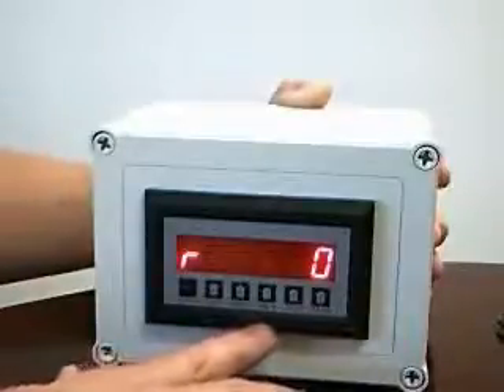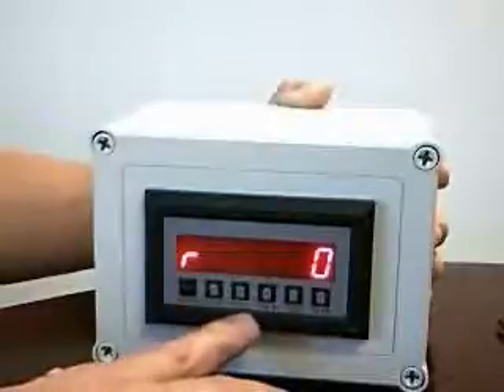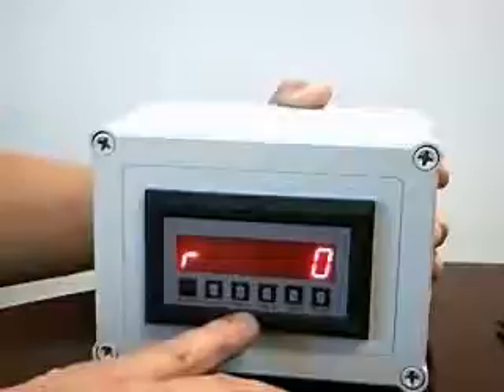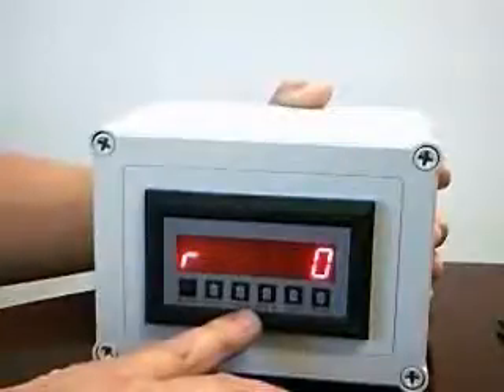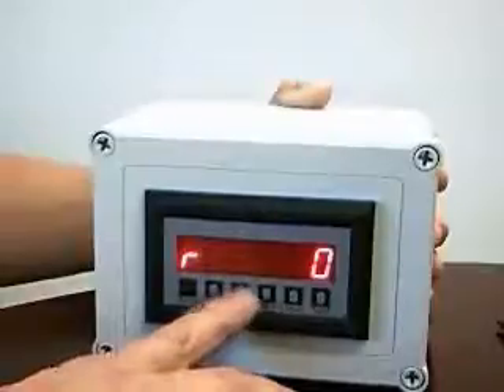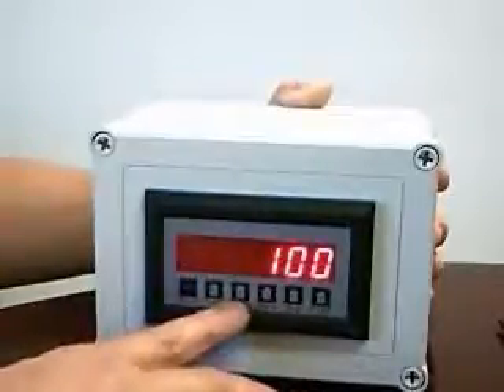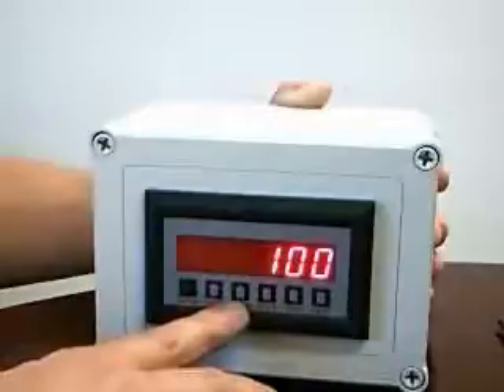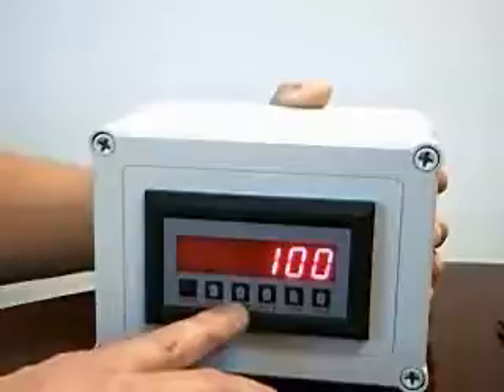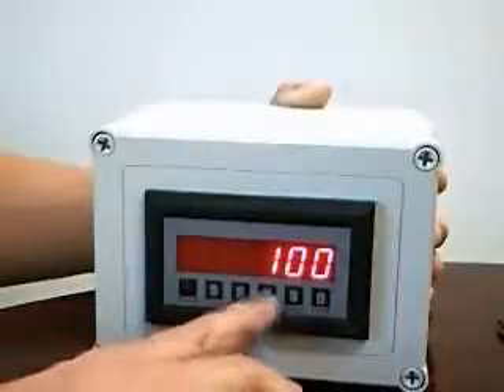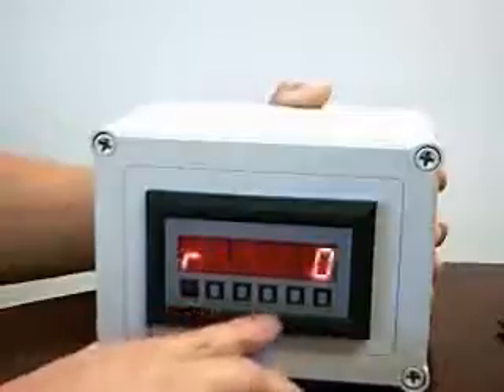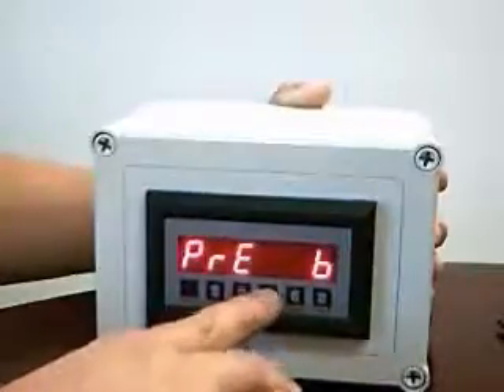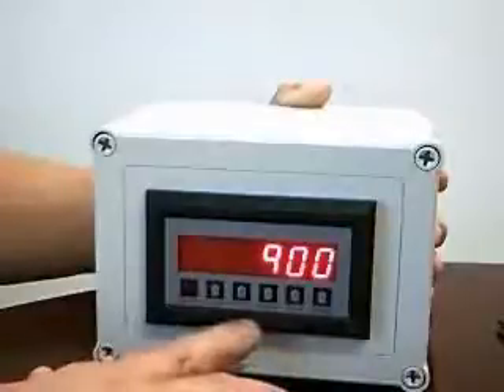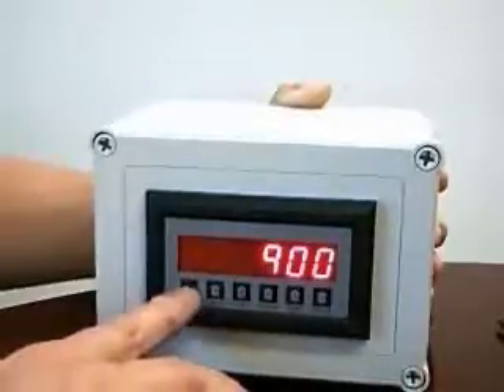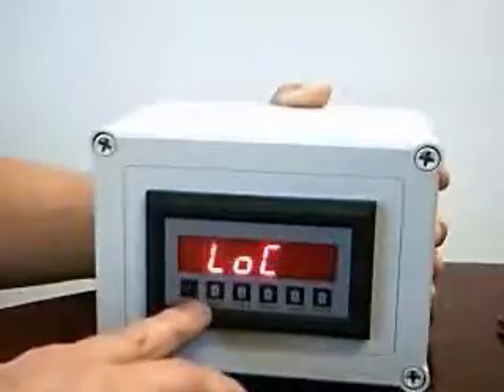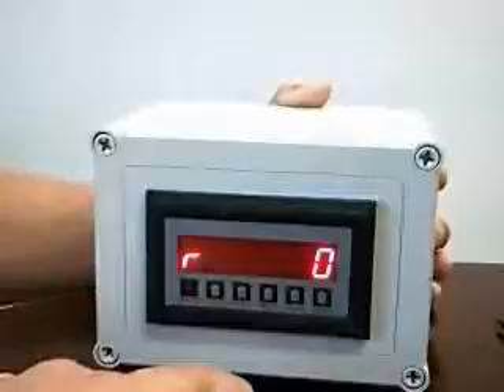There are 2 alarm points on this, and the alarm points themselves can be shown by pressing the keys labeled either pre-A or pre-B. Let's look at the set point for the A alarm. First, it'll show you the value as a pre-A, and then the number immediately changes to show you the alarm point. Similarly, if we press the pre-B button, it'll show us the value on the pre-B. Pressing enter or any other key returns us the display of the rate.